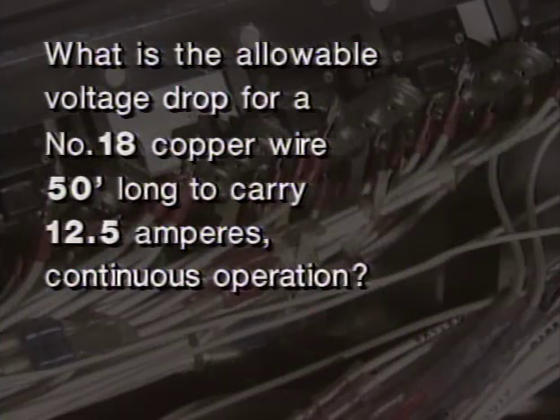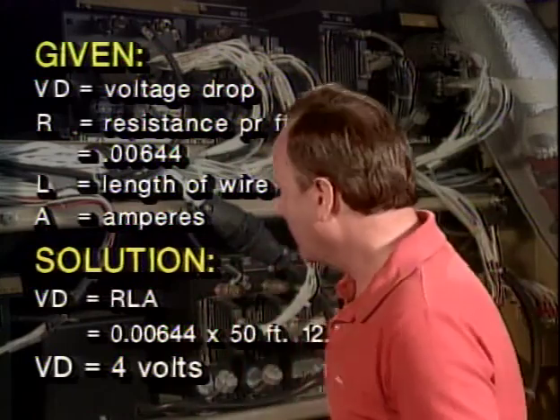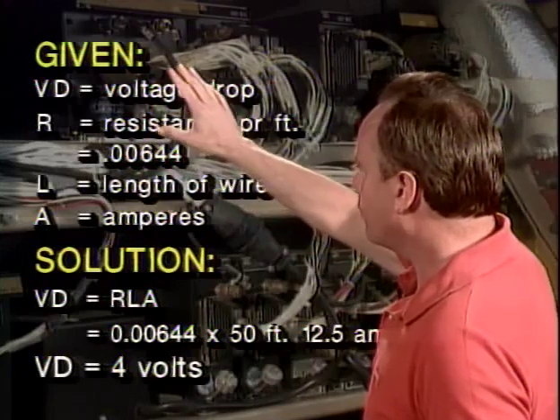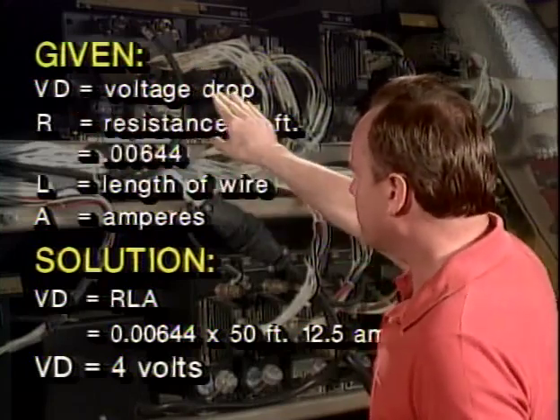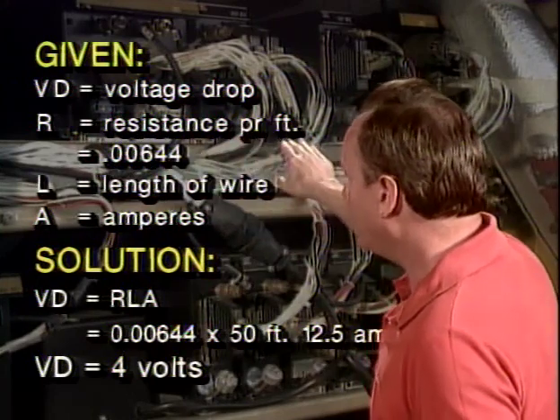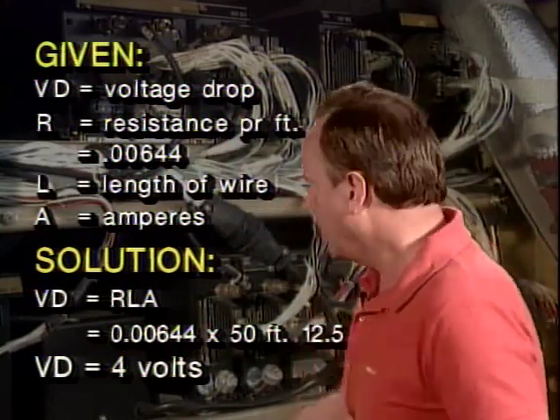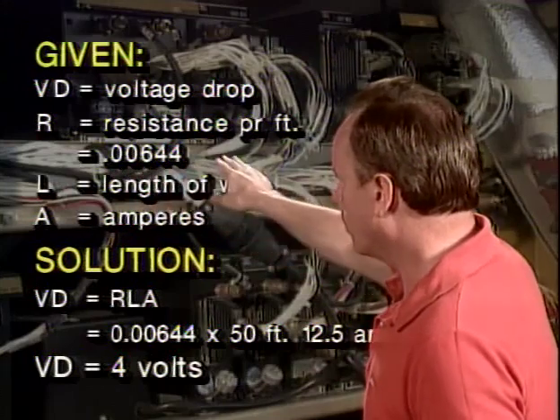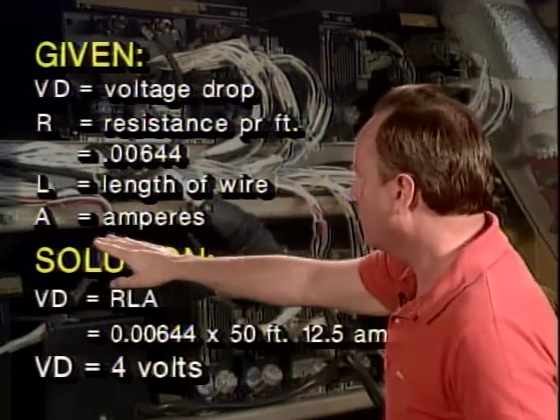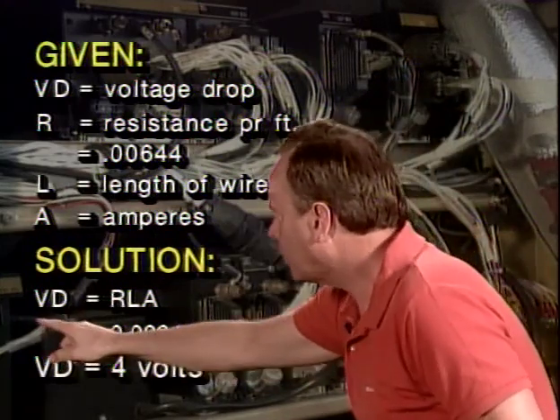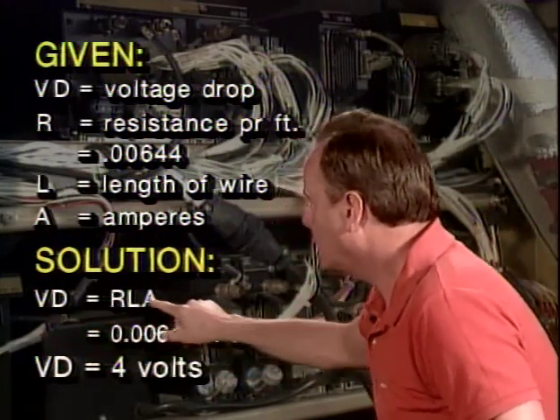Now let's take a look at a question they're going to ask us about this. They're going to say, what is the allowable voltage drop for a number 18 copper wire that's 50 feet long, and it's to carry 12.5 amperes of continuous operation? You think, oh my goodness, how am I going to answer that? Well, here's what they give you. In the question, they give you the formula. And VD stands for voltage drop. And they give you resistance per foot for that particular wire. And in this particular case, it's 0.00644. They give you the length of the wire and they give you the amperes. And here's the formula. Voltage drop is the resistance times the length times the amperes.